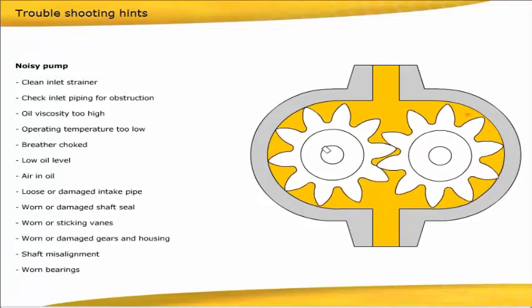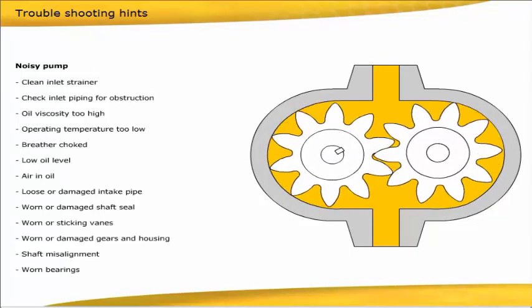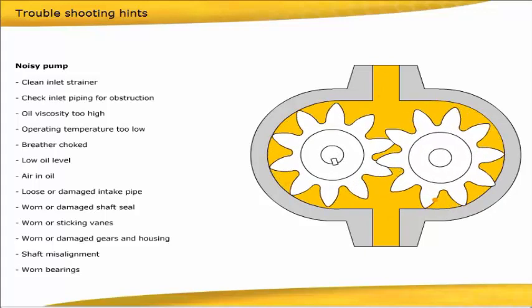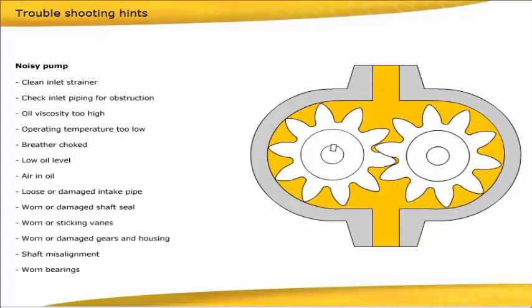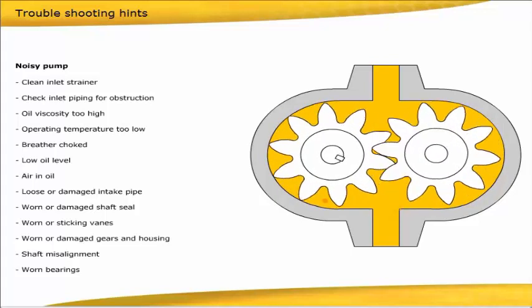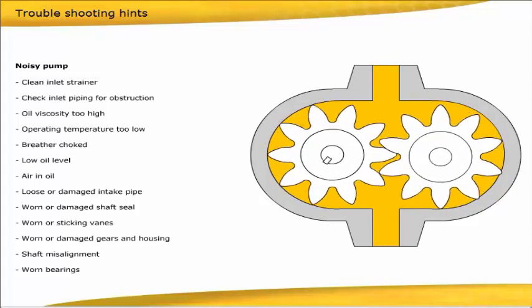Loose or damaged intake pipe. Worn or damaged shaft seal. Worn or sticking vanes. Worn or damaged gears and housing. Shaft misalignment.